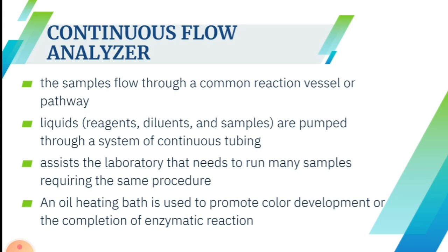Now let's proceed with the continuous flow analyzer. The samples are introduced in a sequential manner, following each other through the same network. A series of air bubbles at regular intervals serves as the separating medium. The internal diameter of the tubing and the rate of flow determine the volumes of sample prior to mixing the reagents and the turnaround time of the result. Continuous flow therefore resolves the major consideration of uniformity in the performance of tests because each sample follows the same reaction path. Continuous flow also assists the laboratory that needs to run many samples requiring the same procedure.